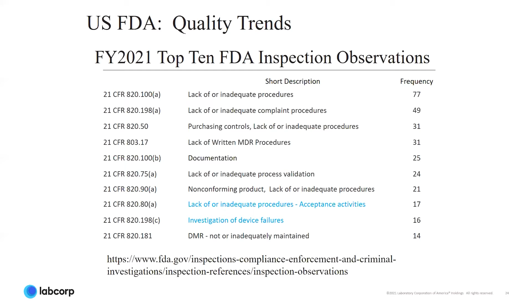What are you doing to show that that's an acceptable lot to accept? And then also investigating any device failures to make the due diligence of whether it's a return device or a failure that you found internally, getting to root cause, showing what caused it to fail. All that investigation piece of that should be well documented as well.